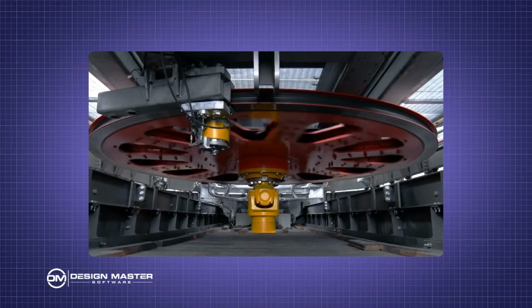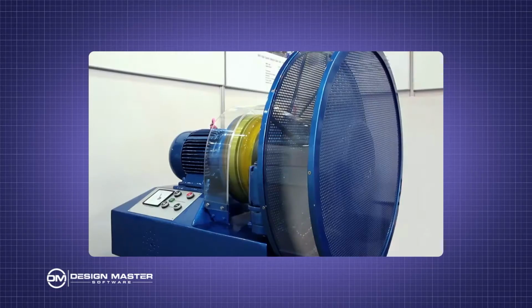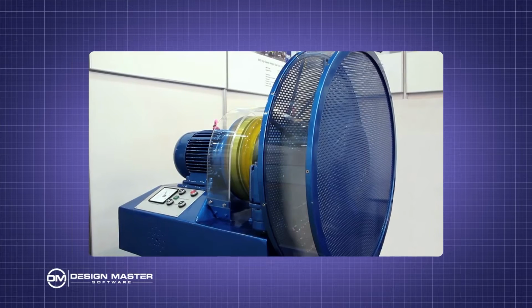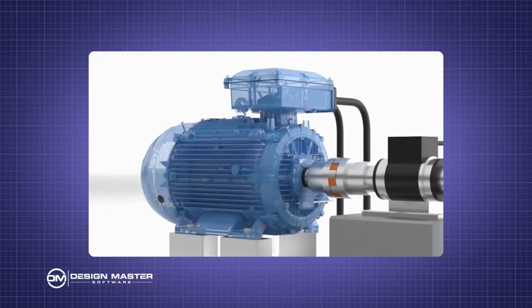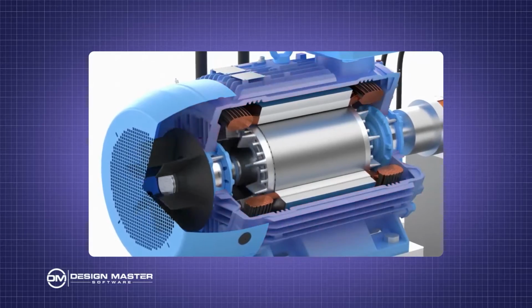Is the brake horsepower always the same for a given motor? Well, if you go back to what the brake horsepower is, it's a function of the load. So no, it's a function of the load, not the motor. The rated horsepower is when you take the brake horsepower up to a point where the current in the windings matches the full load current. The current is chosen for a motor based on the heating effect and the temperature that the windings get to, because at the end of the day, it's the insulation that's going to break down if it gets too hot. And so you can only take the current up to a rating that the insulation can handle. And that's pretty much how the rated horsepower gets set for a motor.